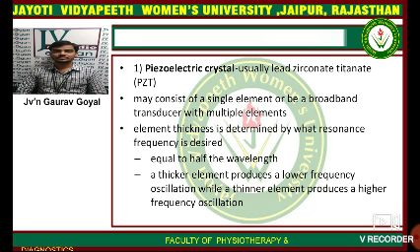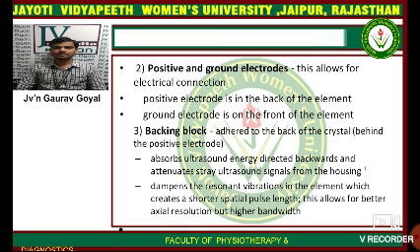The piezoelectric crystal, usually lead zirconate titanate (PZT), may consist of a single element or be a broadband transducer with multiple elements. Element thickness is determined by the resonance frequency desired, equal to the half wavelength. A thicker element produces a lower frequency oscillation, while a thinner element produces a higher frequency oscillation.